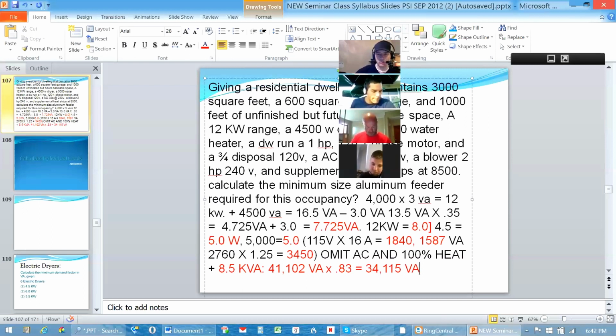Okay, so I'm going to then turn around and divide that number by 0.240, or if you're doing it as volt amps to the kVA, it'd be divided by 240 volts. It gives you 142.14 amps. No matter what your decimal point is, you're always rounding up to the next larger size wire anyway. So effectively, that's 143 amps is what I'm going to put down here just for reference. So I'm looking at a value of 143 amps.